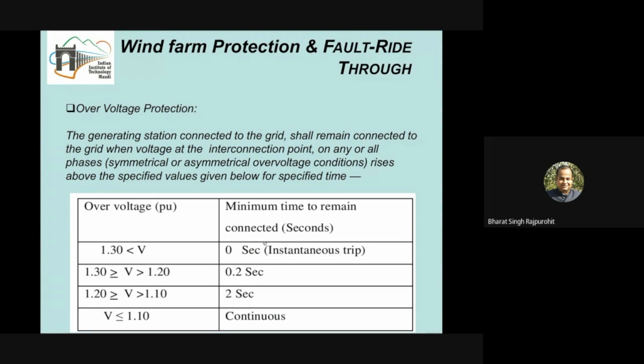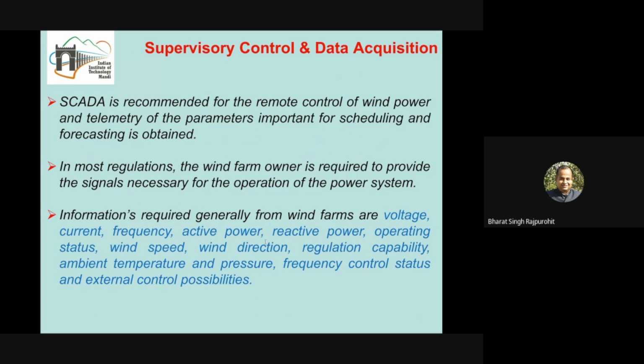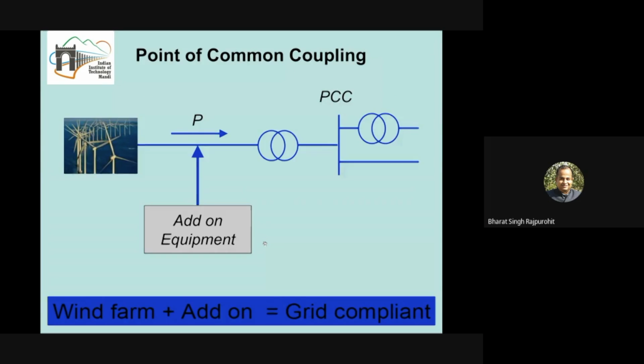Then an over voltage protection scheme is also given in the Indian electricity grid code, which says that if the voltage level goes above 30% of the nominal voltage, then an instantaneous trip can occur. But if it goes up to 1.10 of the specified voltage level, then continuous operation is expected. This is how the high voltage ride through, HVRT, is also prescribed. Fine. Then let me come to the power quality.